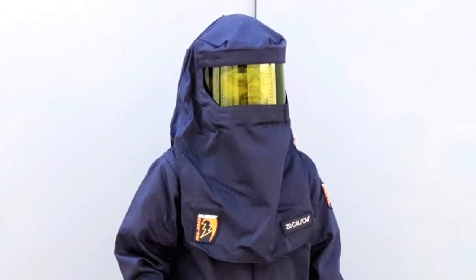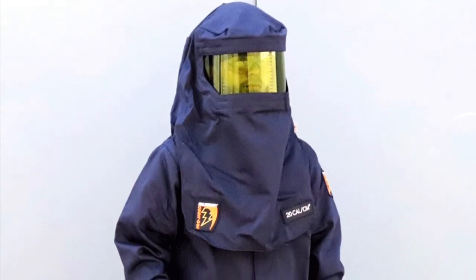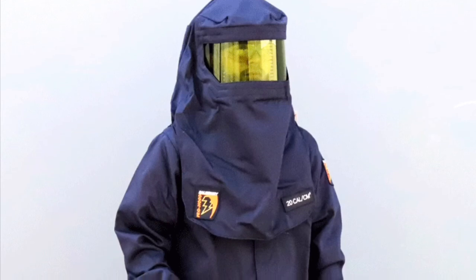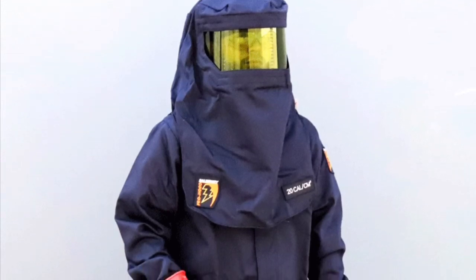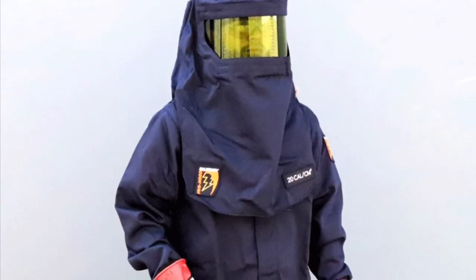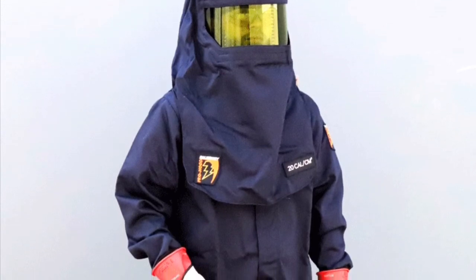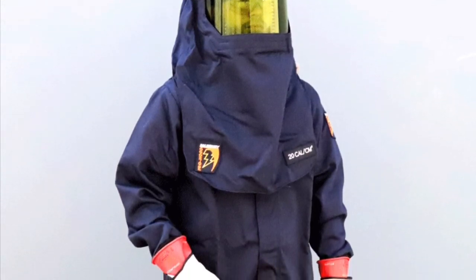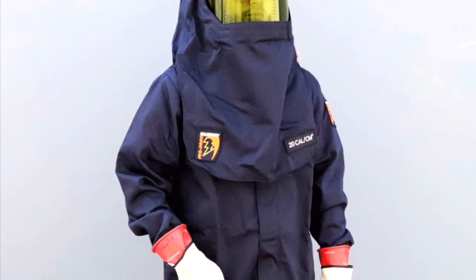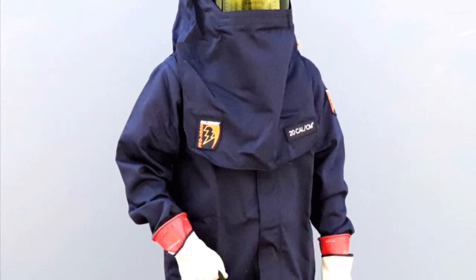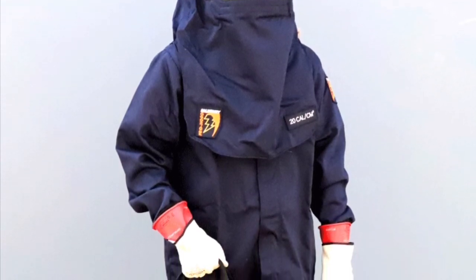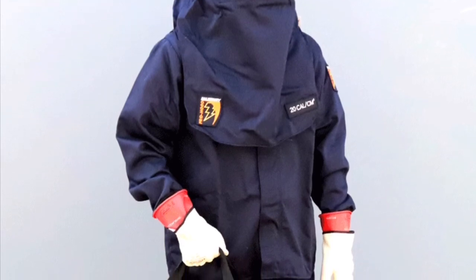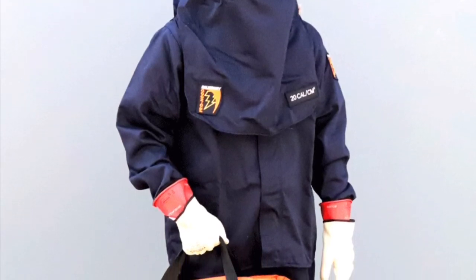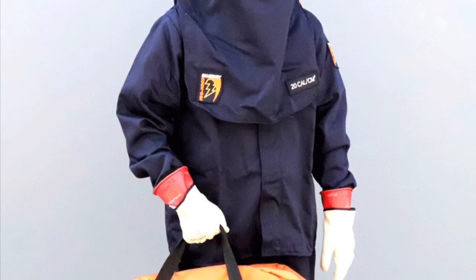Work clothing or arc flash suits that are contaminated or damaged to the extent that their protective qualities are impaired shall not be used. Protective items that become contaminated with grease, oil, or flammable liquids or combustible materials shall not be used. Any flammable soiling or contamination on the surface of the arc-rated clothing can reduce or even void the arc rating of the apparel. The clothing must also be free from tears, cuts, or rips. Garments that are not suitable for use must be removed from service.